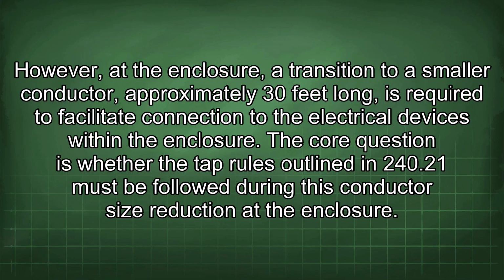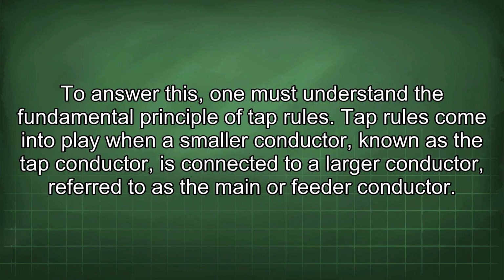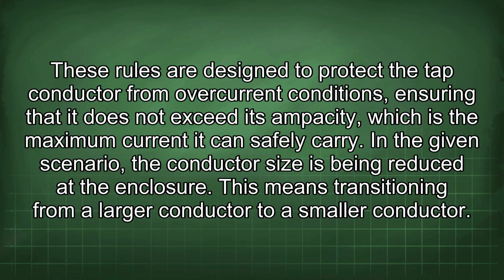The core question is whether the tap rules outlined in 240.21 must be followed during this conductor size reduction at the enclosure. To answer this, one must understand the fundamental principle of tap rules. Tap rules come into play when a smaller conductor, known as the tap conductor, is connected to a larger conductor, referred to as the main or feeder conductor. These rules are designed to protect the tap conductor from overcurrent conditions, ensuring that it does not exceed its ampacity, which is the maximum current it can safely carry.